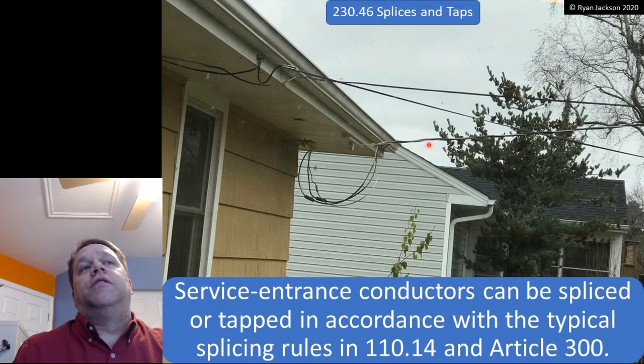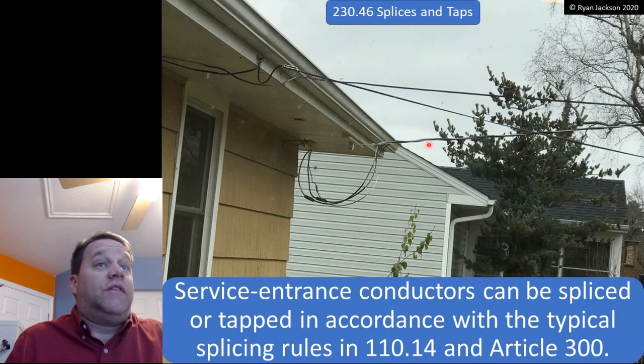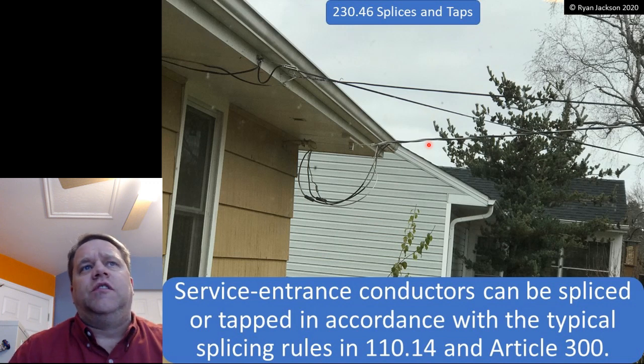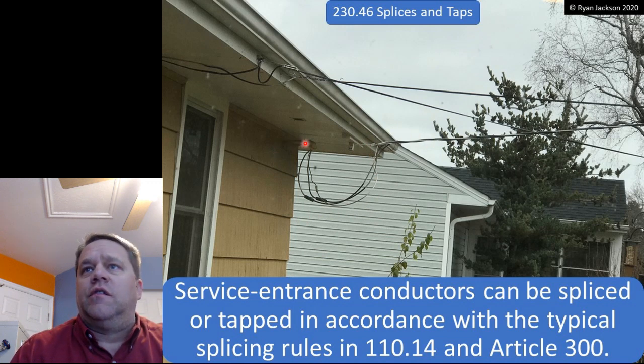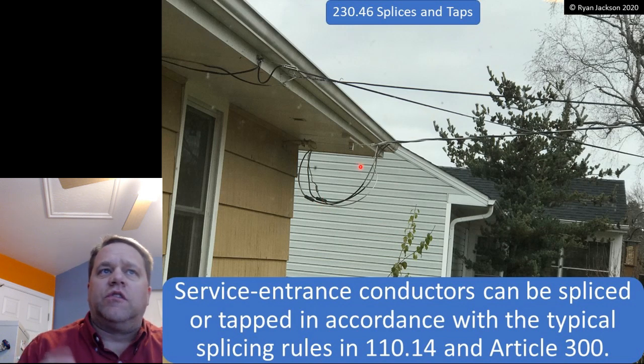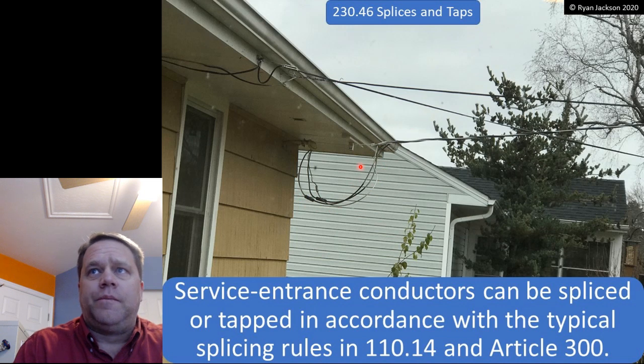A lot of people think that you can't splice service conductors, and that's not true. It never has been true. You can absolutely splice service conductors. How would you make this connection if you couldn't splice service conductors? These are service entrance conductors coming out of the house, and they're spliced to the service drop or to the overhead service conductors. So you can splice service conductors, that's fine.